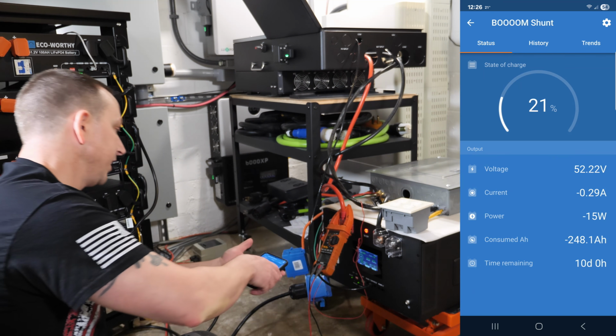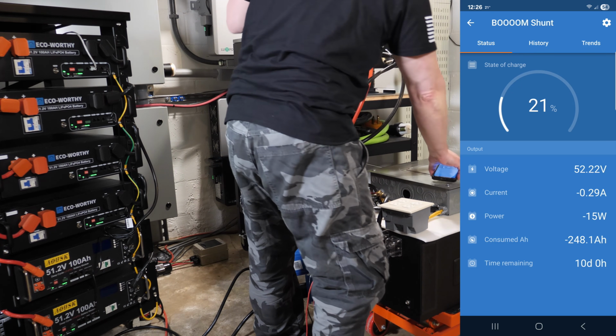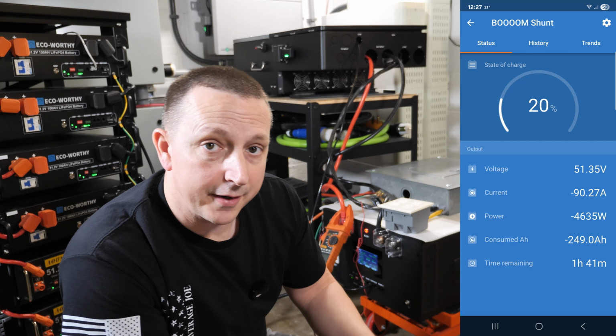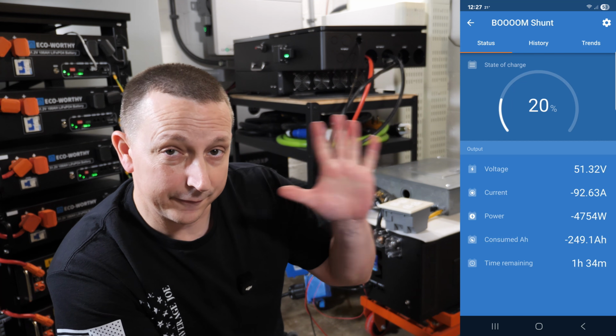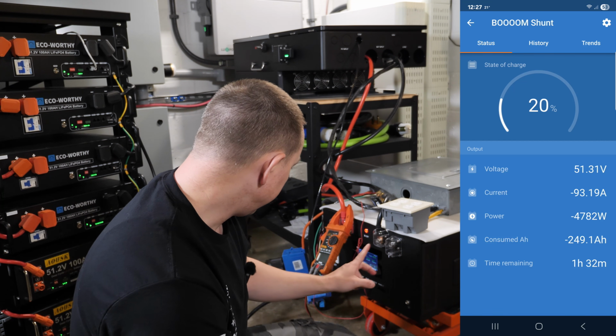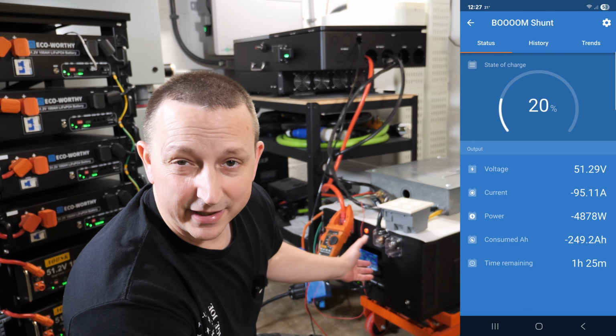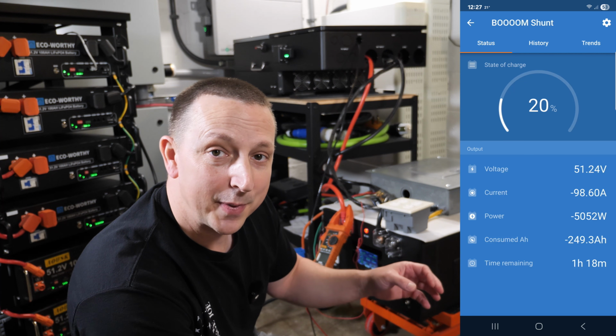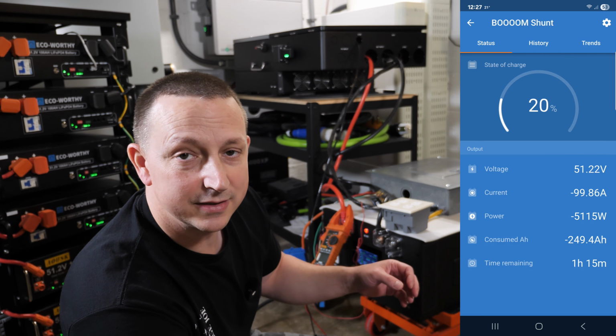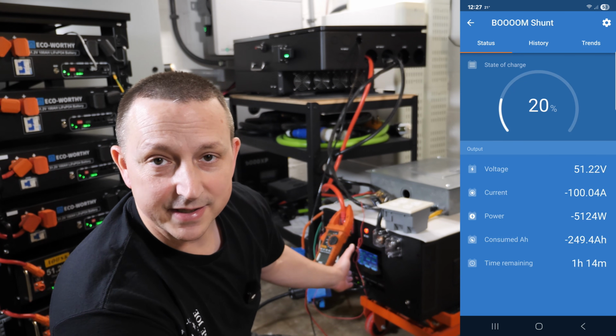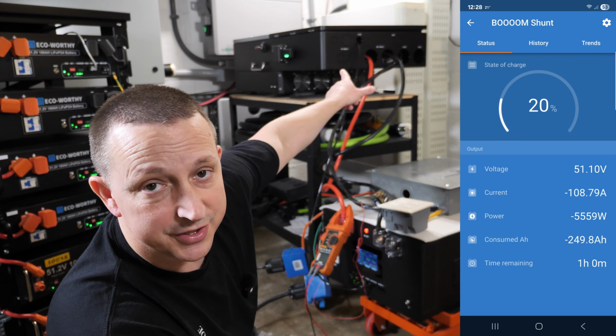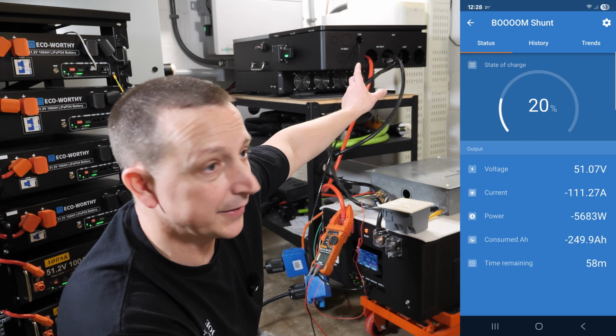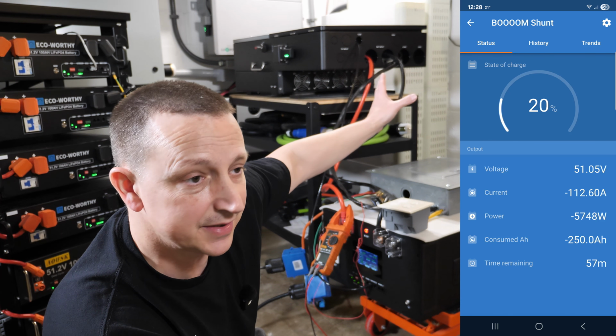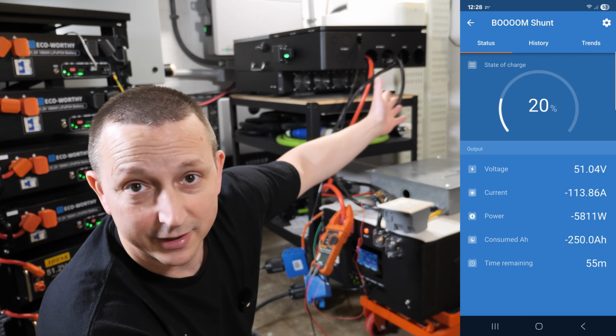I'm going to change the inverter back over to lead acid. So the off-grid cutoff on the inverter was set for 5%, and that's going off of what the battery kind of thinks it is. But since I changed the capacity rating from 314 to 320, that's obviously off. So what I did for the inverter is just change it to lead acid real quick, and the voltage is set for 40 volts, and hopefully it'll shut off around there.